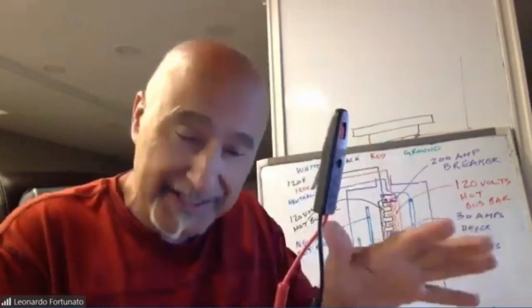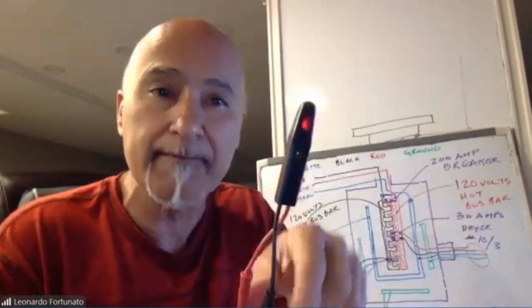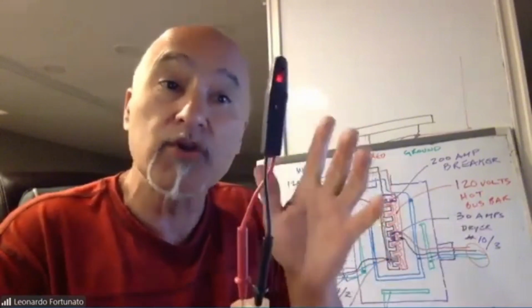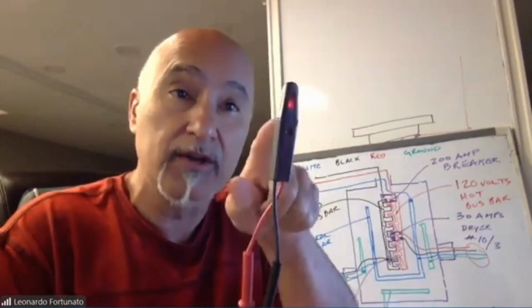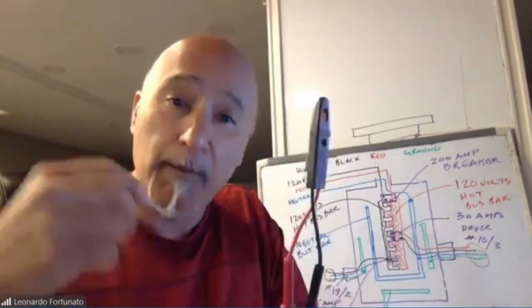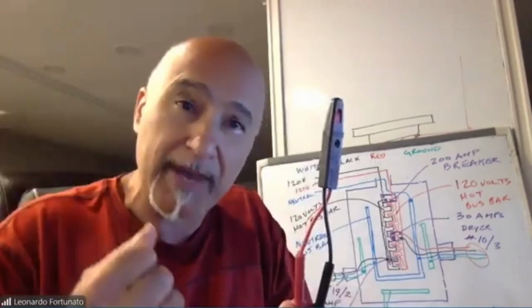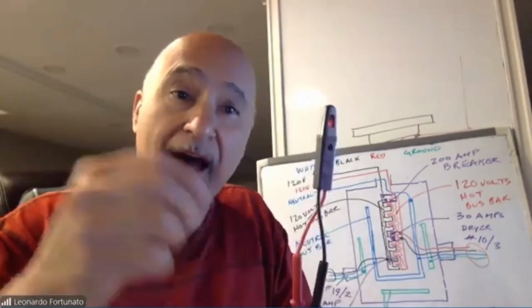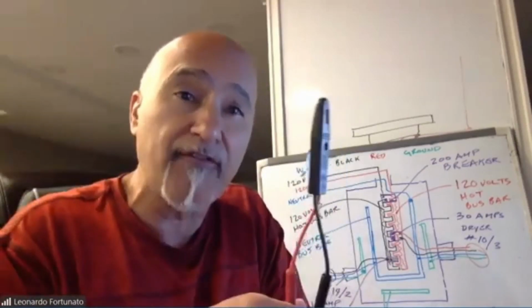Again, when you're going to turn power off somewhere, you want to make sure the power is off. You can use a simple tester like this one. Test it somewhere where you know there's power, so you know it's functioning properly. Then put it where you need to turn the power off. Have someone turn the breaker off, since you're not always going to be in the same location. When that light goes off, you know the power is off.